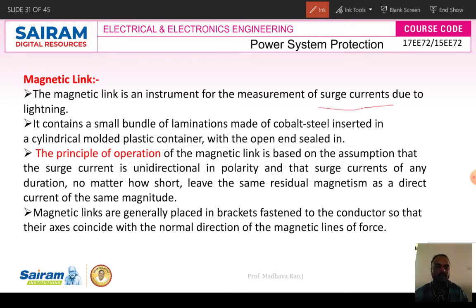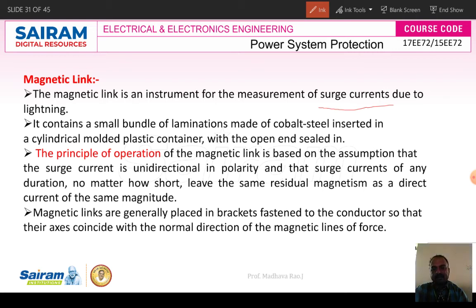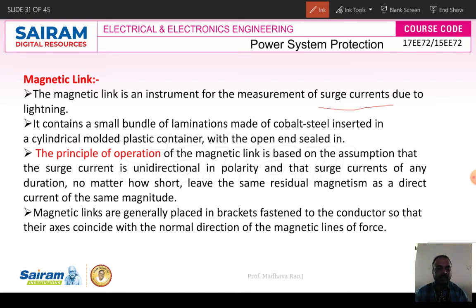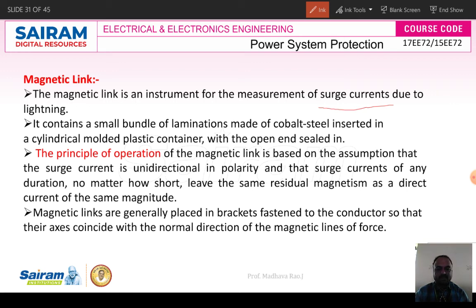Surge currents can be measured by using the magnetic link. It contains a small bundle of laminations made up of cobalt steel, inserted in a cylindrical molded plastic container with the open end sealed. It is like a transformer core — with silicon steel laminations used in transformers, but in the magnetic link we use cobalt steel laminations.